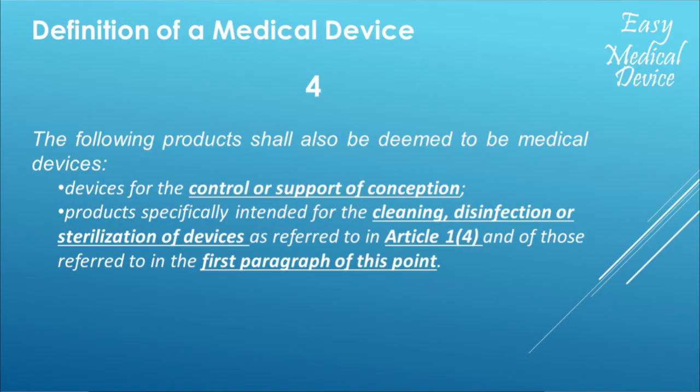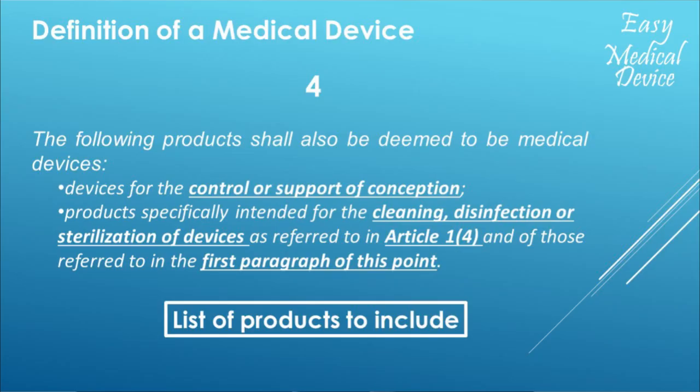We arrive at the fourth block. It says: 'The following products shall also be deemed to be medical devices.' Which products? Devices for the control or support of conception, and products specifically intended for the cleaning, disinfection or sterilization of devices as referred to in Article 1, Paragraph 4. So mainly products used for cleaning, disinfection or sterilization of devices. I reduced this to: a list of products to include. You will see later that there is a full annex of additional products with no medical purpose that we should also include.